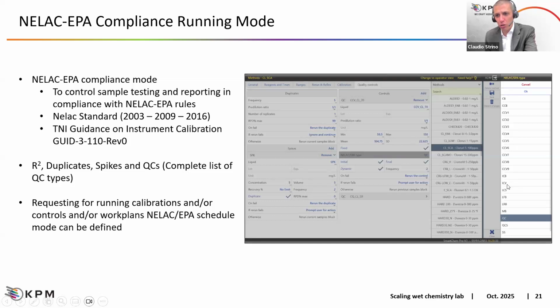For example, if we define ICV, automatically the software will only schedule those controls before running samples, because it's the initial calibration verification. While if defined as CCV or CCB, they will be managed dynamically, so in between samples and at the end of the analytical routine.